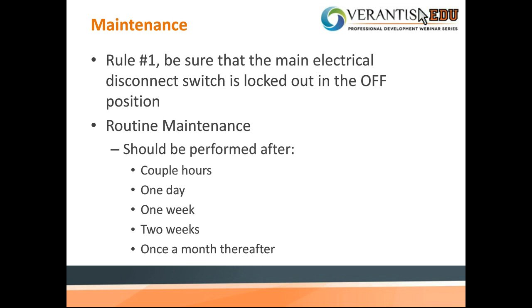Rule number one of maintenance is to be sure that the main electrical disconnect switch is locked out in the off position. We definitely don't want anybody getting inside of the fan with the power not turned off. Most facilities have a lockout procedure; make sure it's followed. That's the main thing. We don't want to hear of any issues happening with our fan that could have easily been prevented. So, routine maintenance should be performed after a couple hours, after 1 day, after 1 week, after 2 weeks, and then once a month thereafter.